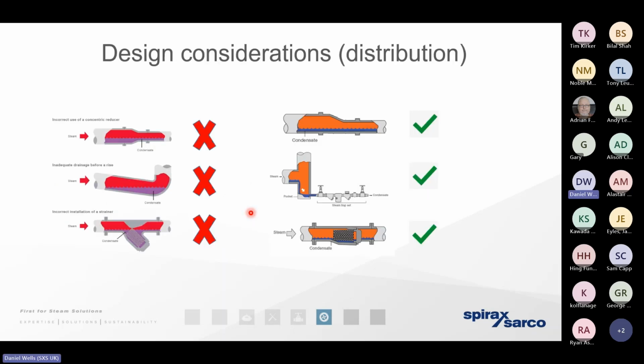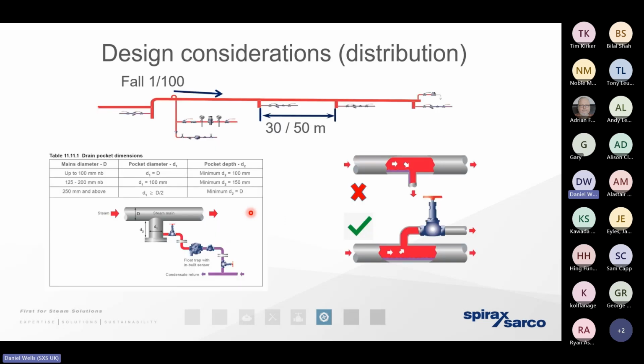So one of the most important things we can do is apply that best practice in order to ensure that the condensate can move out of the infrastructure very, very quickly. We don't want that condensate to sit there for too long, because by doing so, we're encouraging the mechanical issues like erosion, corrosion, and water hammer. But the steam's going to degrade, and as it degrades, it's going to have less energy contained within it. And as it gets wetter, it's more likely to condense, thereby reducing the mass of steam that's going to be available for the process.